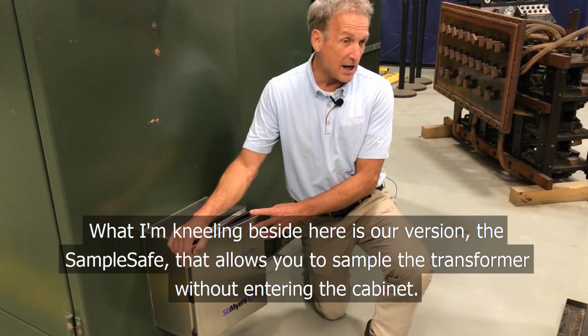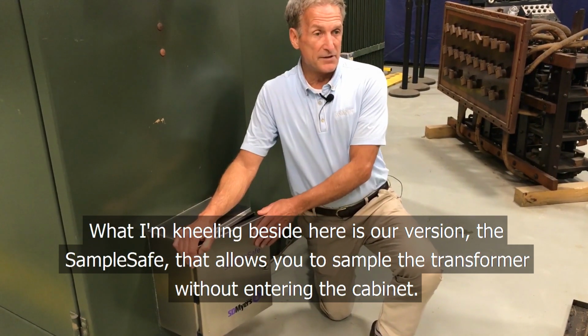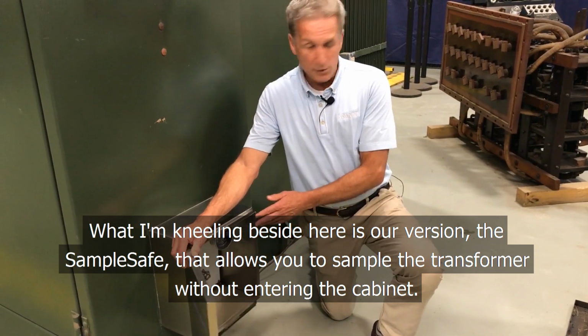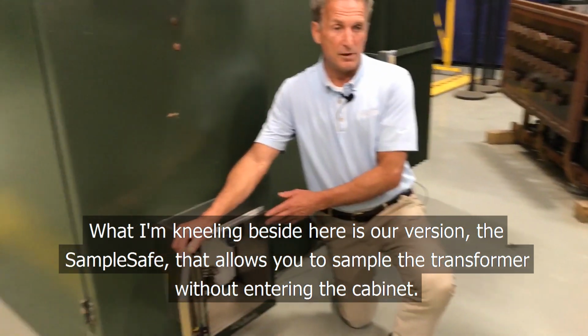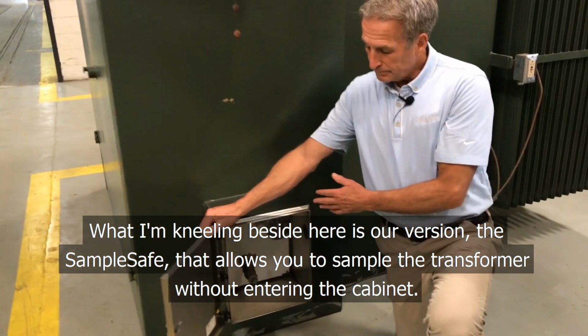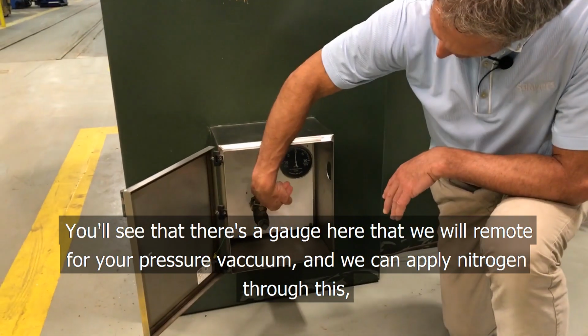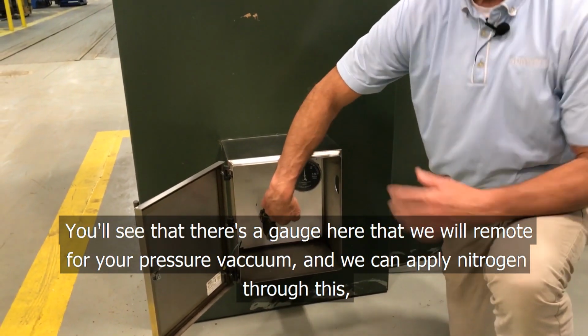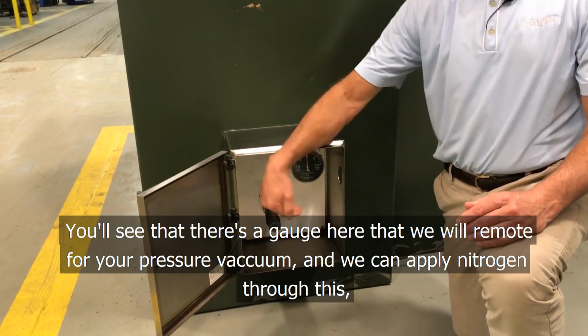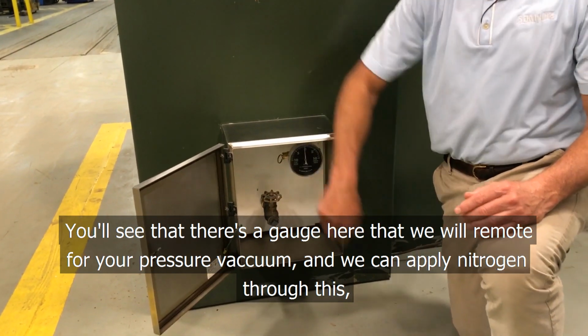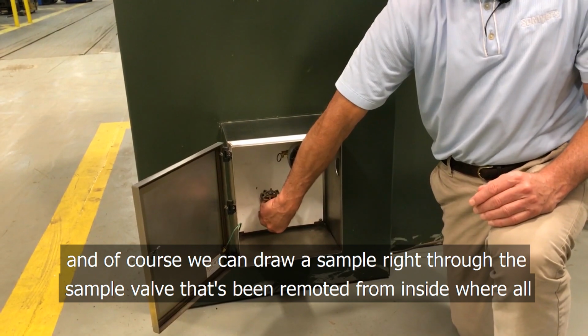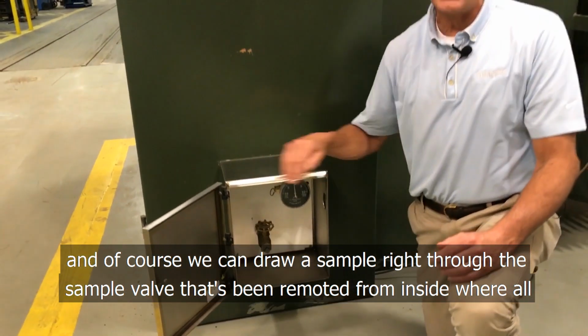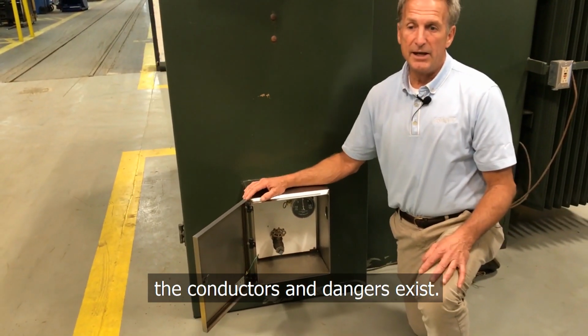What I'm kneeling beside here is our version of the Sample Safe that allows you to sample the transformer without entering the cabinet. You'll see that there's a gauge here that we will remote for your pressure vacuum, and we can apply nitrogen through this, and of course we can draw the sample right through the sample valve here that's been remoted from inside where all the conductors and dangers exist.